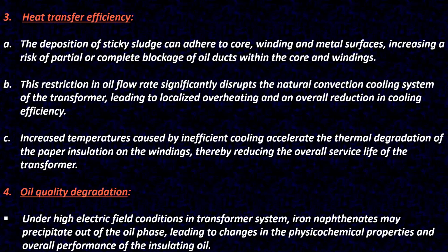This restriction in oil flow rate significantly disrupts the natural convection cooling system of the transformer, leading to localized overheating and an overall reduction in cooling efficiency. C. Increased temperatures caused by inefficient cooling accelerate the thermal degradation of the paper insulation on the windings, thereby reducing the overall service life of the transformer.